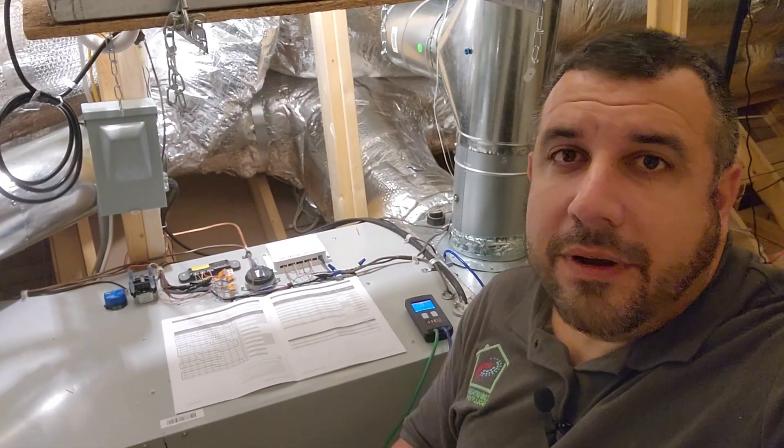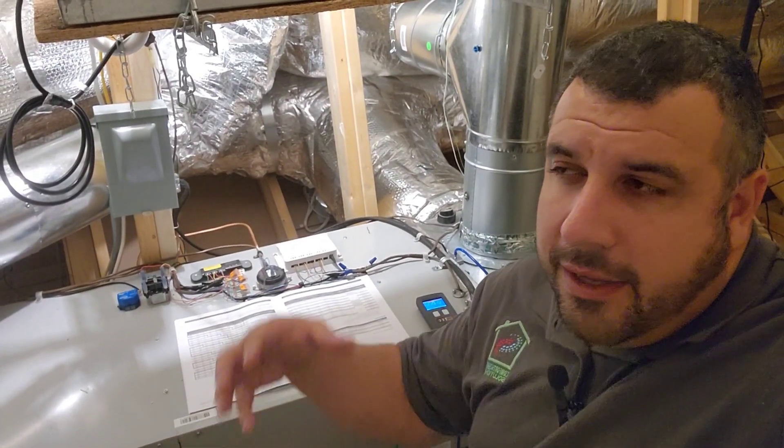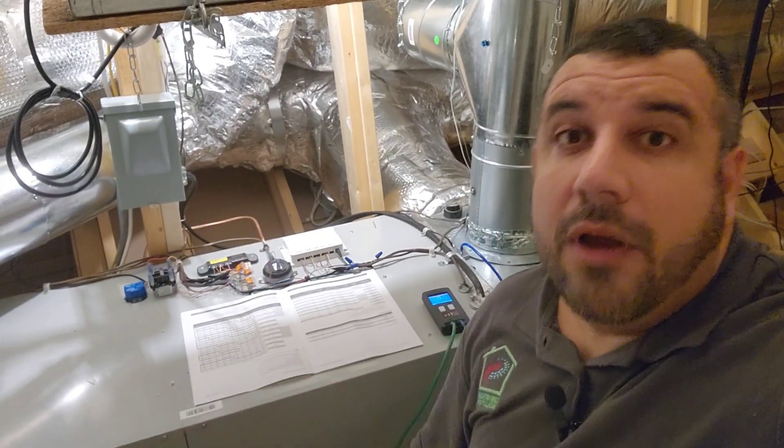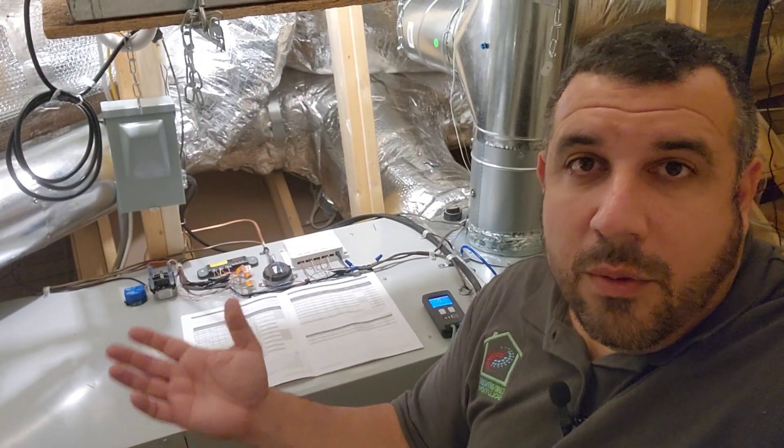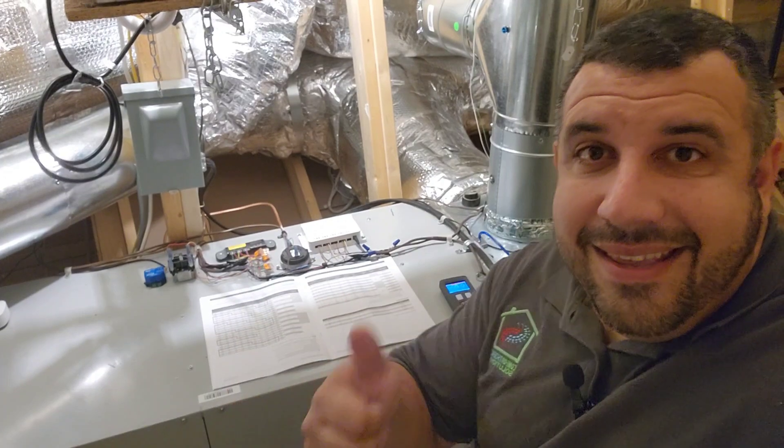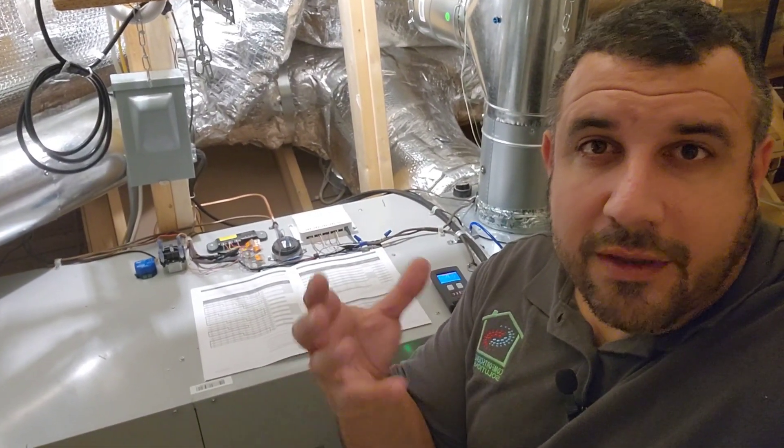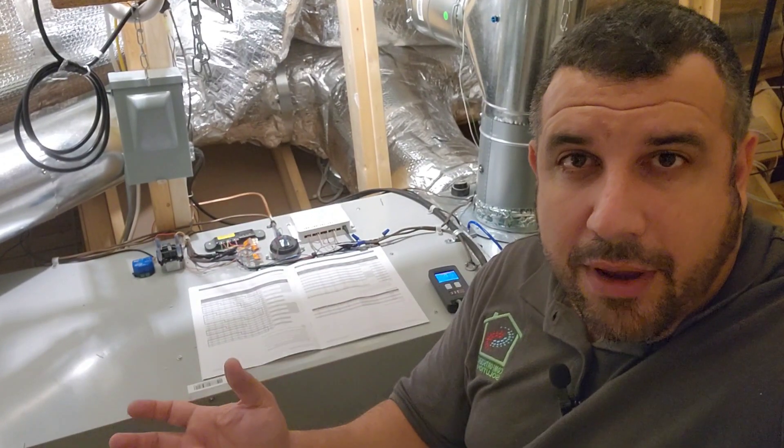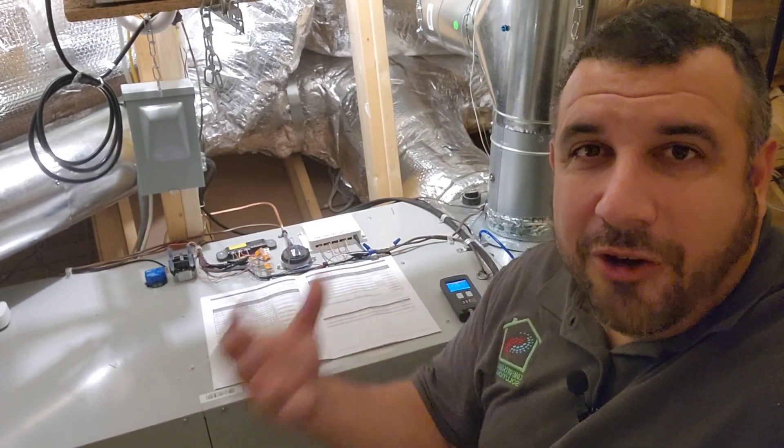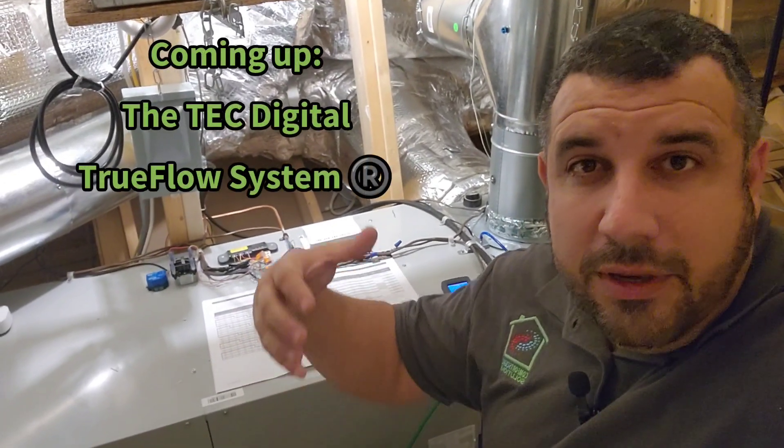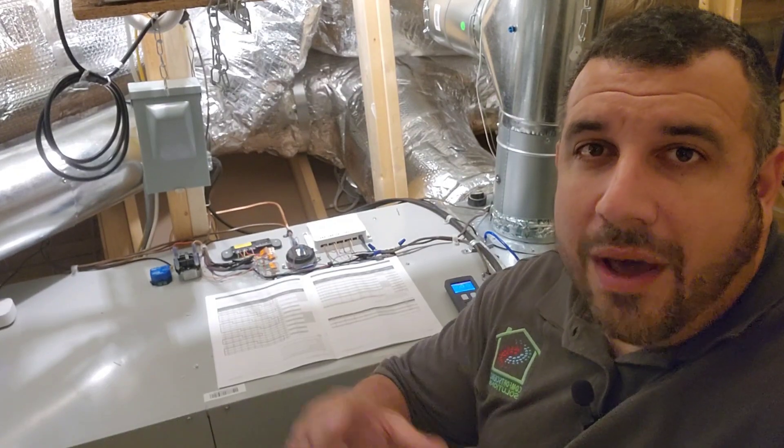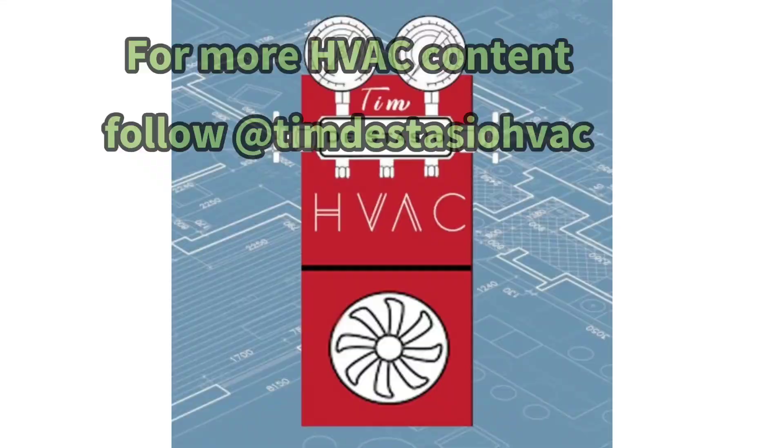All right. So just to review, static pressure is a very quick way to be able to quantify airflow. It's sort of a rough measurement. It's not exact. For one thing, your static pressure test ports may not be in an ideal situation because you're not working with an ideal duct system that gives you a lot of straight line duct with very little turbulence. Sometimes you just got to use what you got, which is going to throw that reading off just a little bit. Another thing that you got to worry about, especially with older equipment is, is the coil dirty? Is the blower dirty? Just a thin film of dust on either of these can directly affect that static pressure reading. And then when you convert that over to airflow using the blower chart, it's not going to be the true airflow. A lot of things can throw off that reading. And that's why static pressure, it's quick, it's rough, it's dirty. It'll get you by. It can kind of get you in the ballpark, whether you need to troubleshoot airflow further, whether you can set it aside and maybe look for another reason why there are comfort or other issues with the system, but there are better ways to quantify airflow. And I'm going to get into that in a future video. For now, thanks for watching, and as always, be safe.